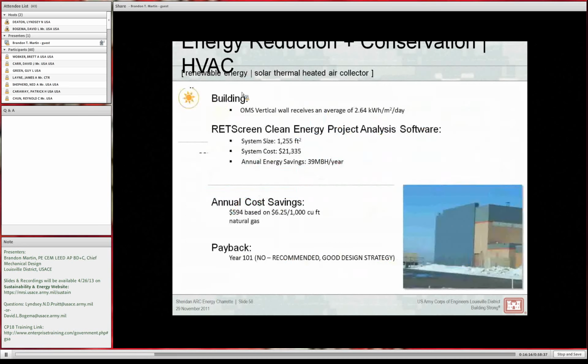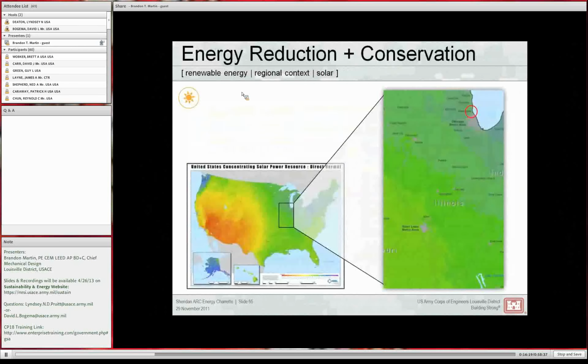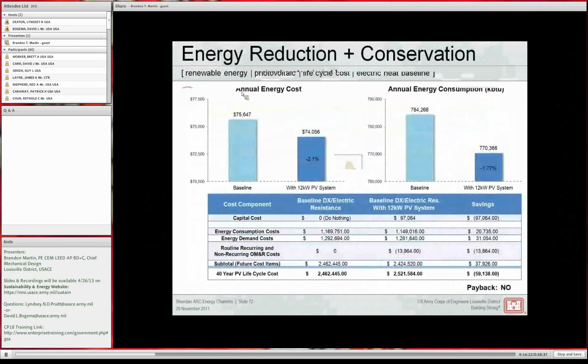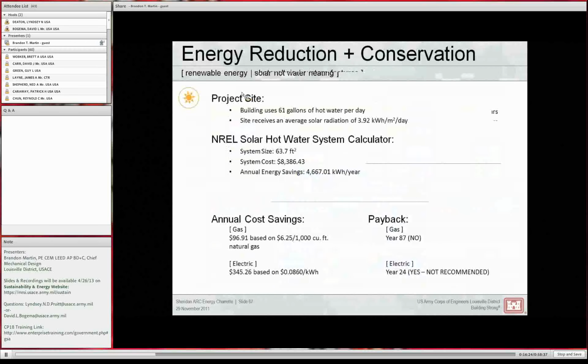We made the opposite decision on renewable energies, like solar hot water heating. We looked at that, and it didn't pay back with a gas baseline, which is what we were going to have. If we had an electric baseline, it would pay back, just because electric rates were so high. So depending on the base and building, if for instance they had no natural gas or would need to run a gas line two miles, you might put in a solar hot water heating system because that would be life cycle cost effective.